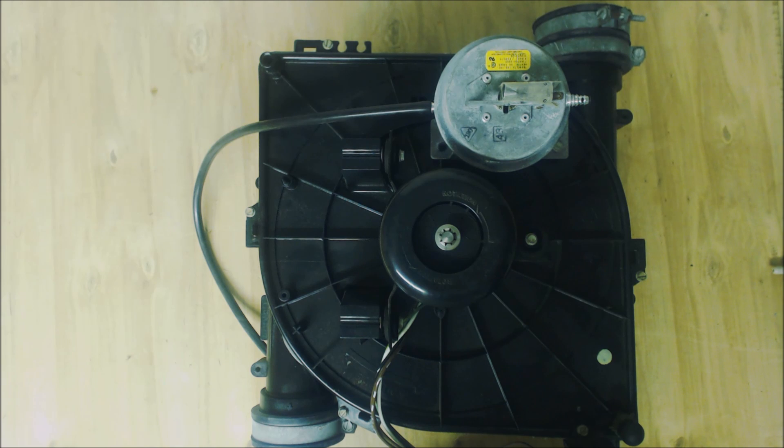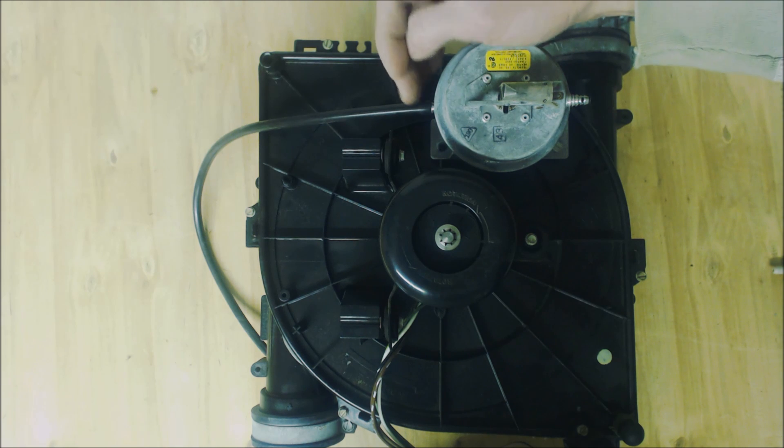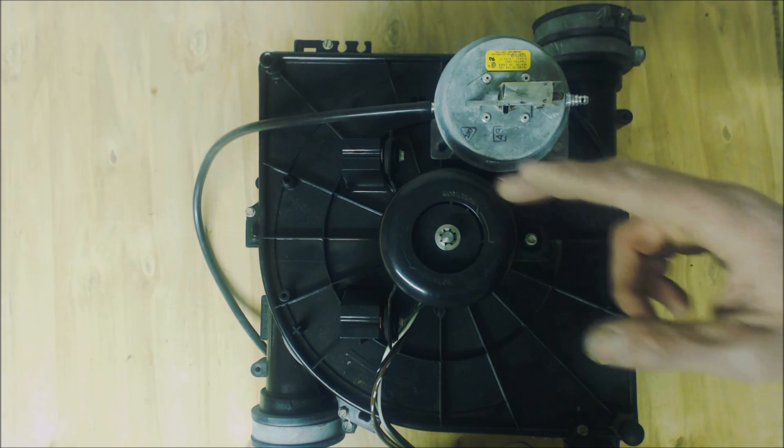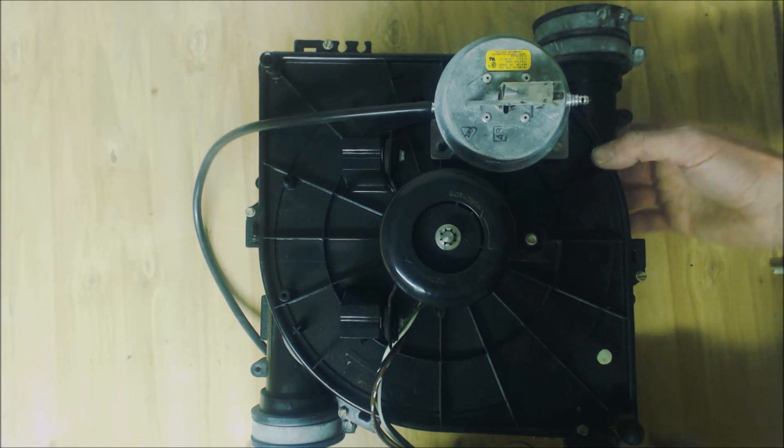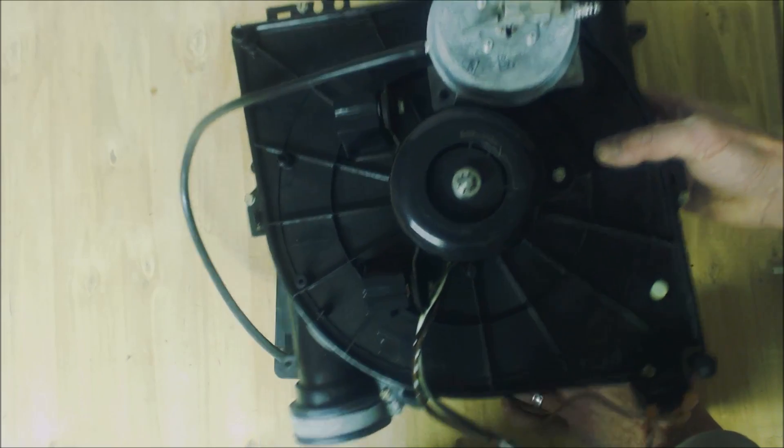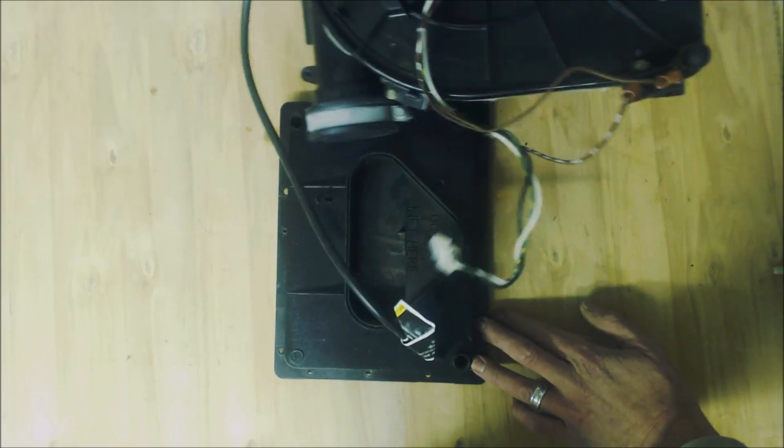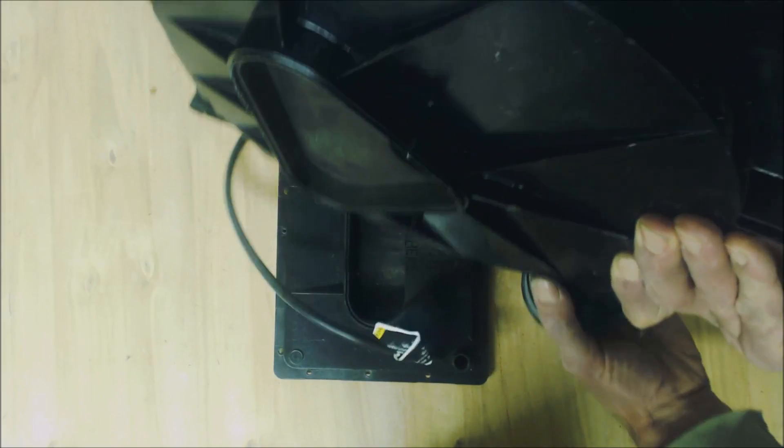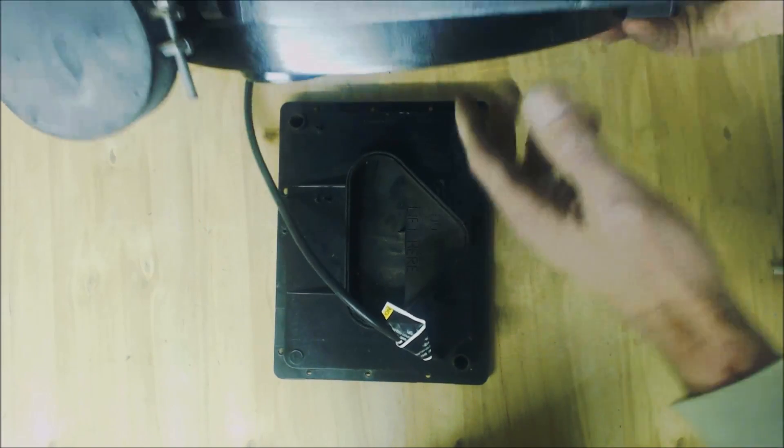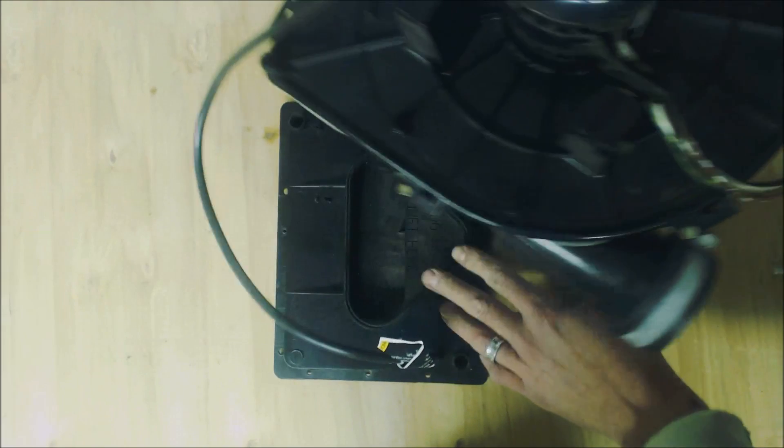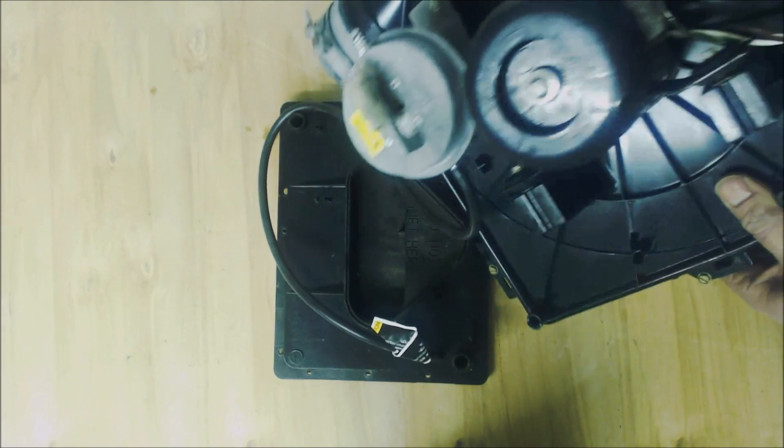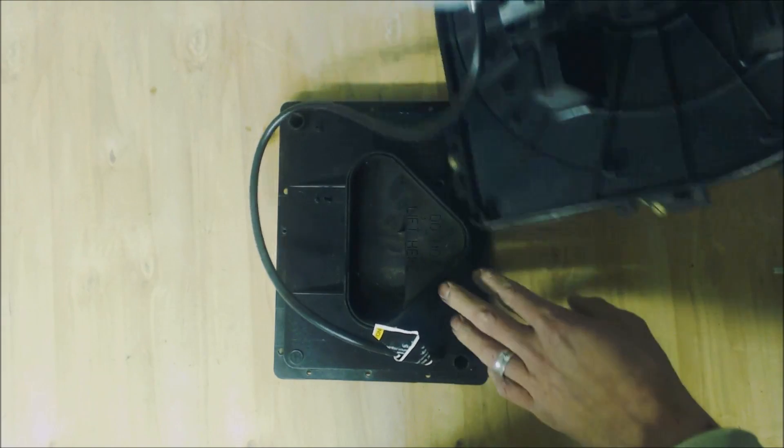So the reason that you have a pressure tube going to the condensate line of a 90% efficient gas furnace is this heat exchanger right back here. This is where you have the inducer motor hooked up right here. This connects to the heat exchanger and here's your tube for your pressure switch. You can see it follows from here all the way over to here.